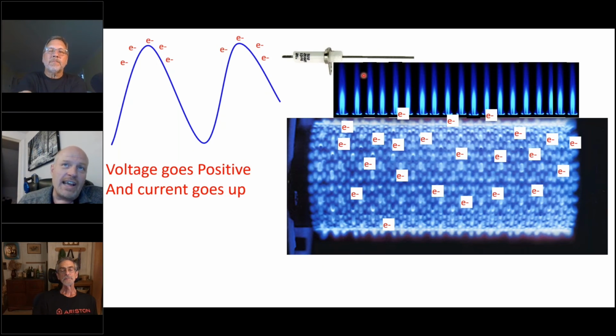and these electrons, and it knows that it sent, for example, 100 electrons out, and it only got 90 electrons back. So the difference between 90 and 100 is 10. So that means the flame signal is 10 microamps, or so is typically how we would measure it.